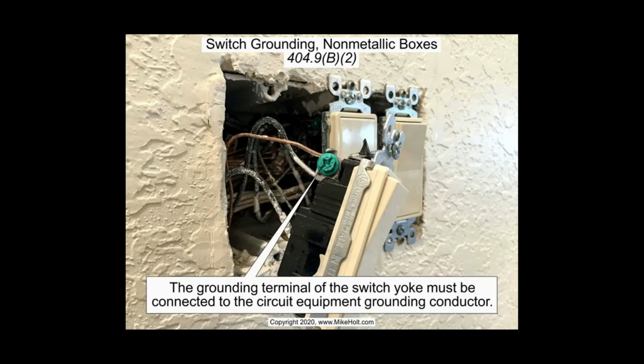Switch grounding, non-metallic boxes. The grounding terminal of the switch or yoke must be connected to the circuit equipment grounding conductor. So if you're using plastic boxes, you don't get a choice. You have to connect this ground.